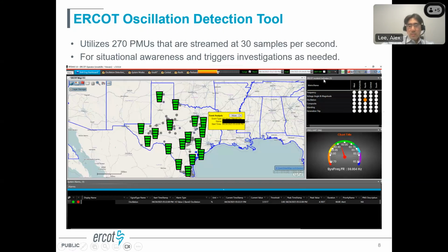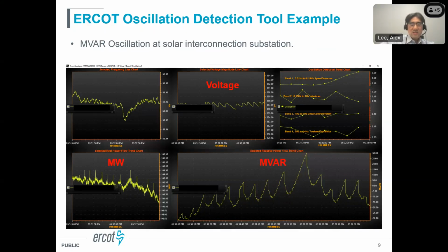On the upper right panel, we categorize different types of oscillations that the system is monitoring, whether it's frequency oscillations, voltage angle or magnitude oscillations, islanding oscillations, or generation trips. We also have different locations shown in the upper left, where the green bars indicate the locations of the PMUs in the ERCOT footprint. Whenever oscillations are detected, a yellow pop-up shows the time point and specific location where the oscillation was detected. That way, our engineers can go in and further look at what kind of oscillation is detected by the system.